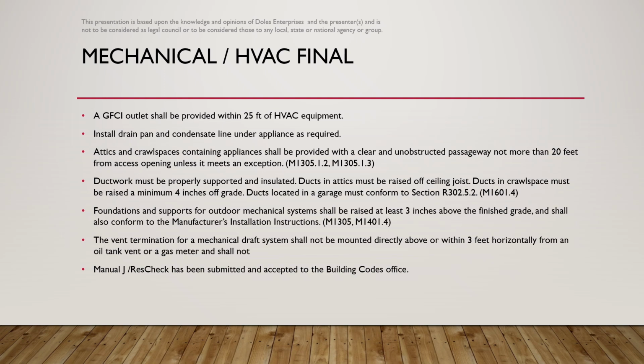Foundations and supports for outdoor mechanical systems shall be raised at least 3 inches above the finished grade and shall also conform to the manufacturer's installation instructions. As a side note, typically we see condensers sitting at grade. They must be raised 3 inches above surrounding grade.